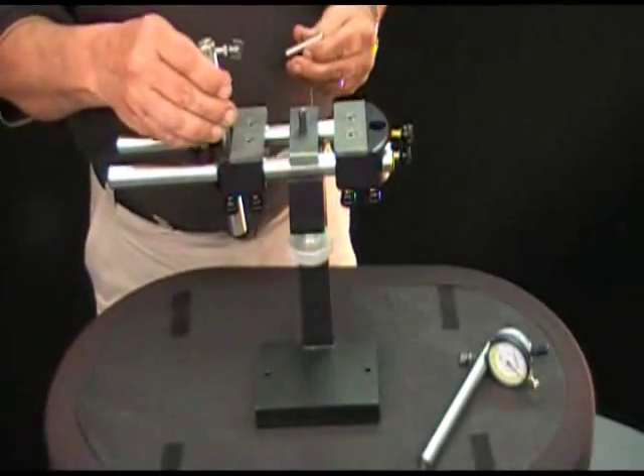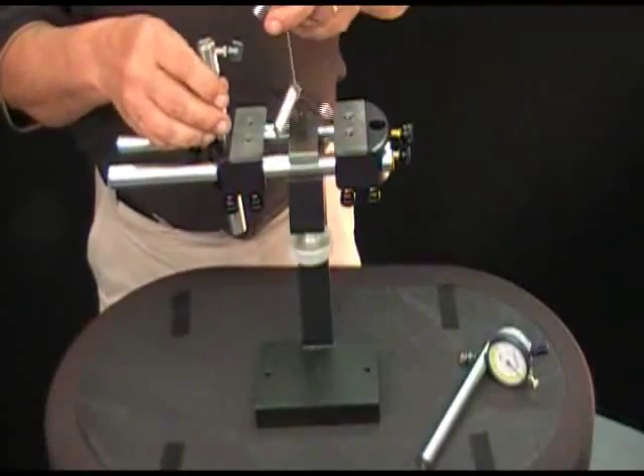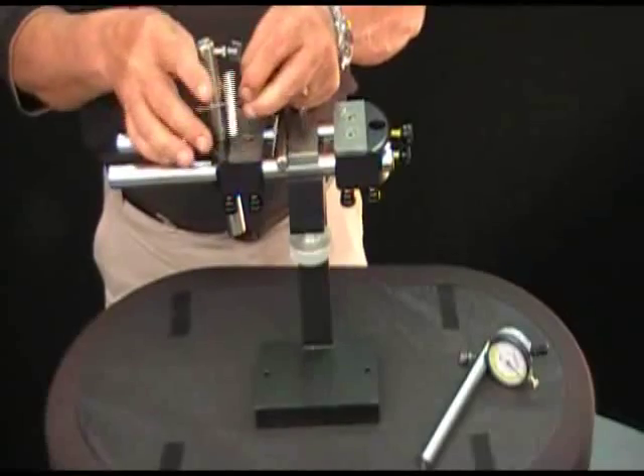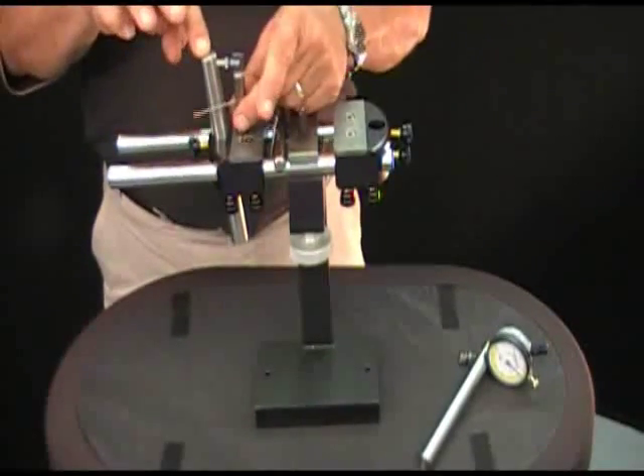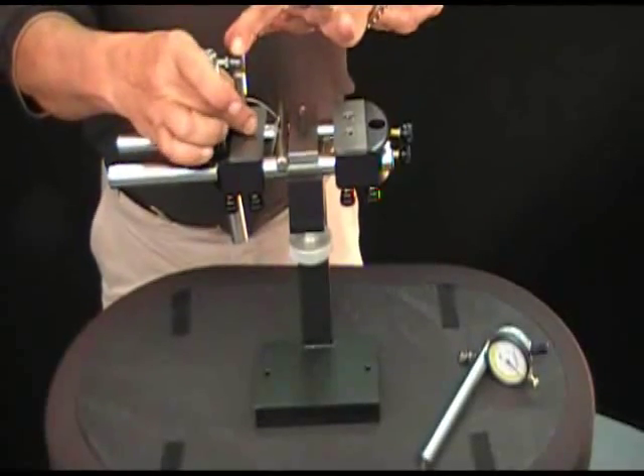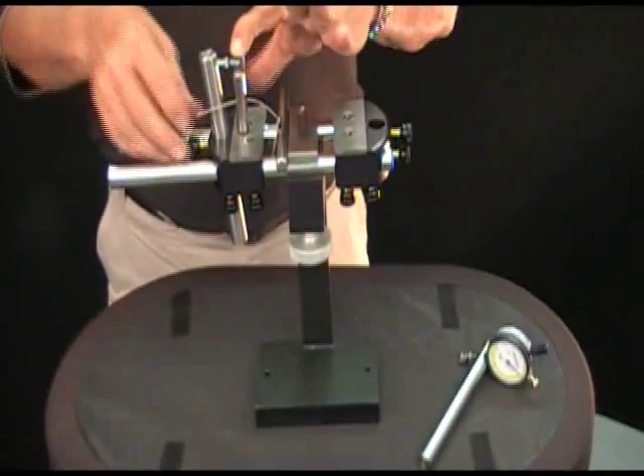The gauge has a ball detent spring plunger in the block that allows us to set the standard down. We're going to use what we call the B standard, it's the short one of the two. I bring it down and I like to put my thumb right over the top of the shoe. Rotate the shoe side to side to get it running parallel with the wear pad and the back of the shoe.